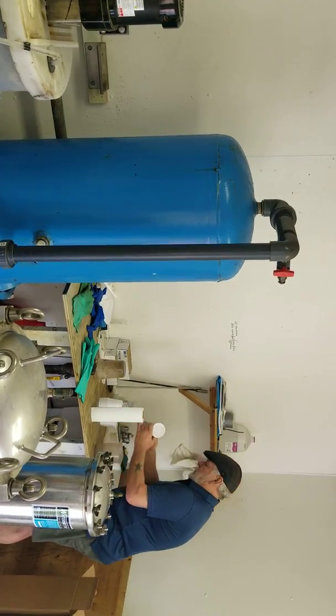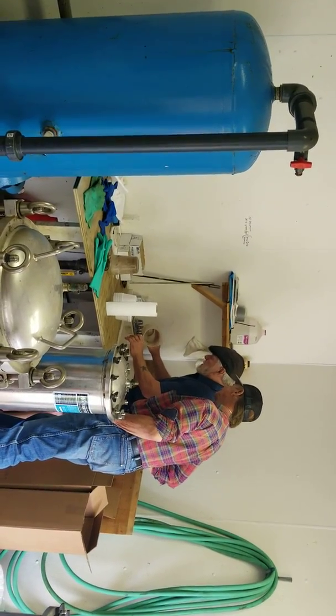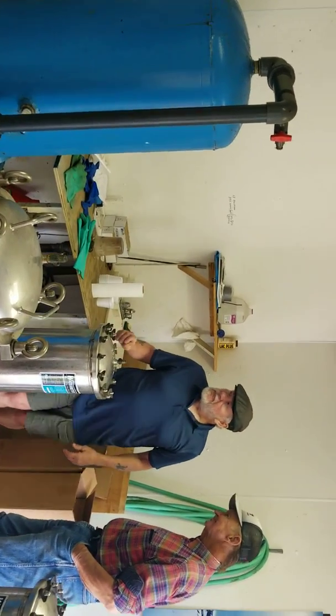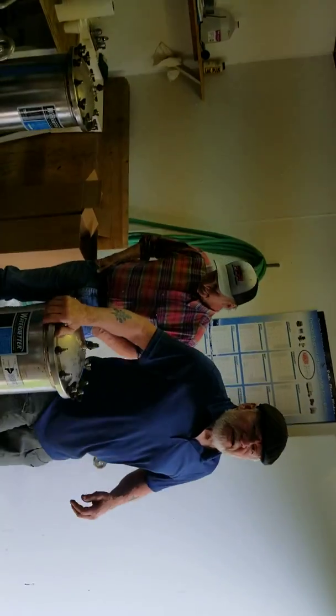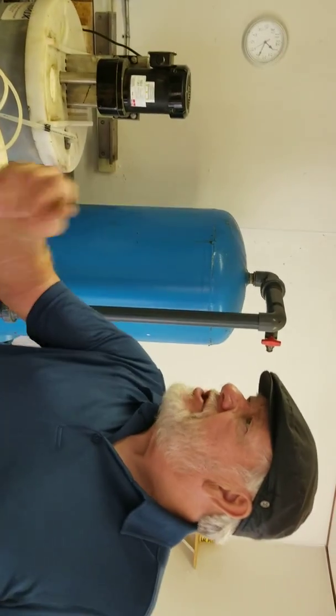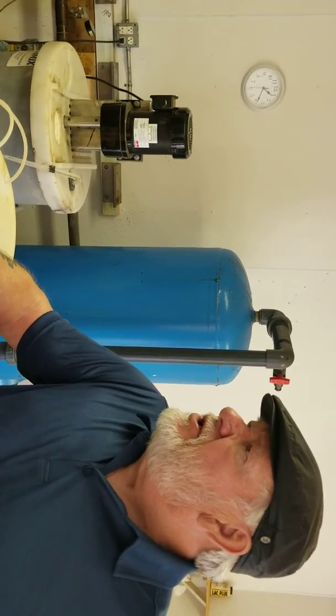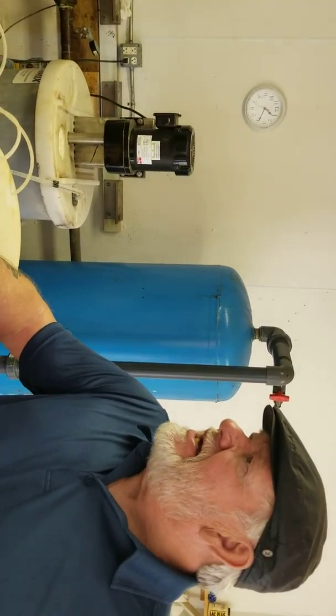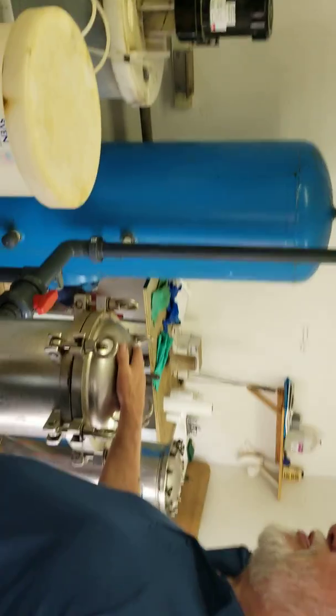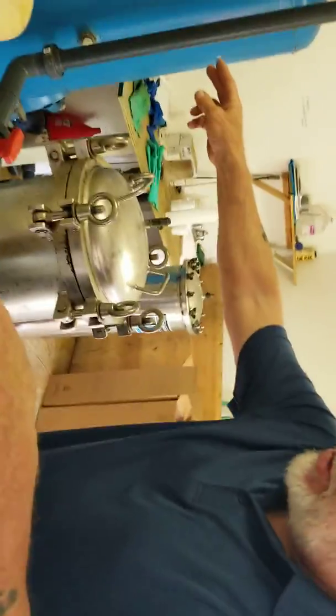First sample that came out of there right now. It's really dark stuff. It's about the size of the head of a stick pin. They're pretty good size, and some of them, of course, will break down into small, almost sand size, and they'll break through. A 20 micron filter picks up probably 90% of it. Then you go to a 5 micron, and continue with the flow.